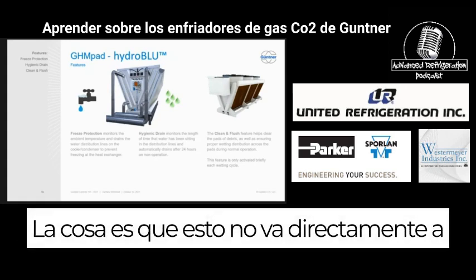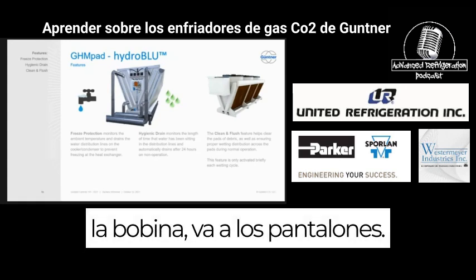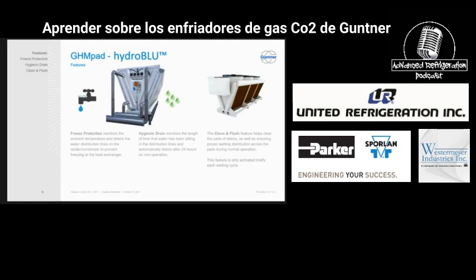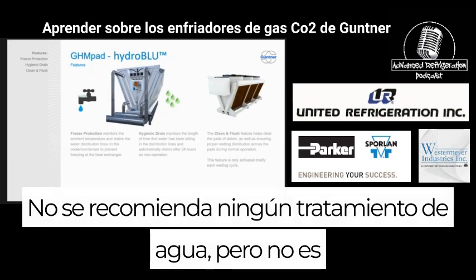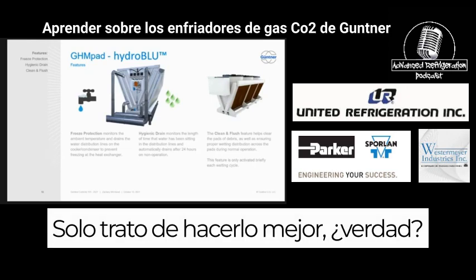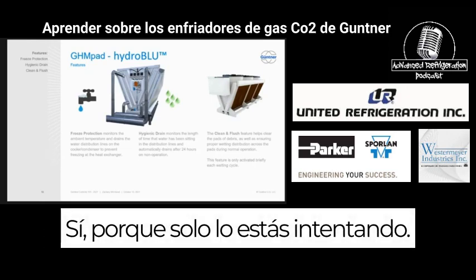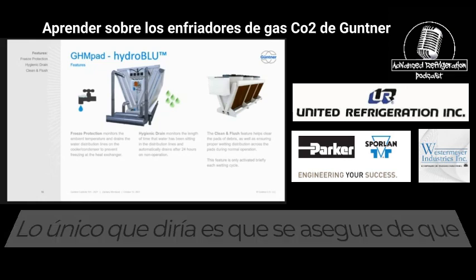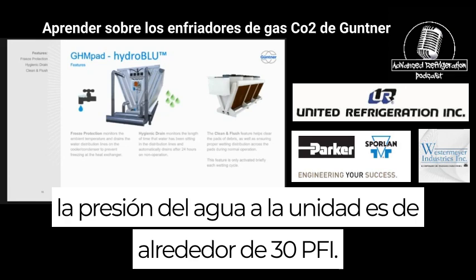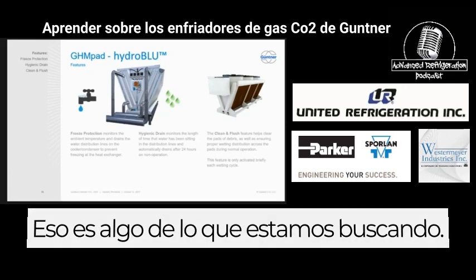The thing is that this isn't going directly onto the coil. It's going onto the pads, so it's not affecting the coil. So no water treatment is recommended, but it's not going to void any warranty if I throw some filters on there, just trying to do better for it, right? Yeah, because you're just trying to improve the water quality. The only thing I would say is make sure that the water pressure to the unit is around 30 PSI. That's kind of what we're looking for.